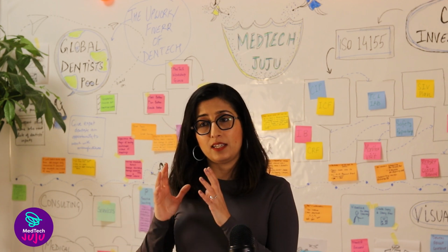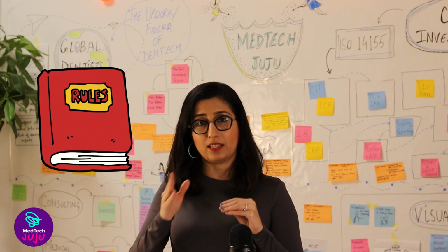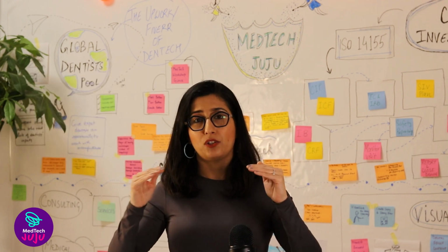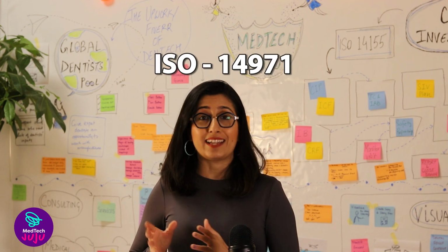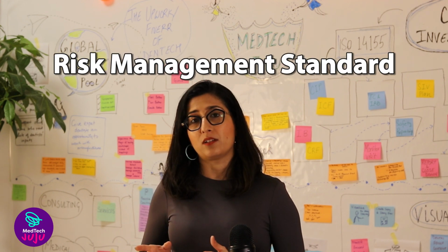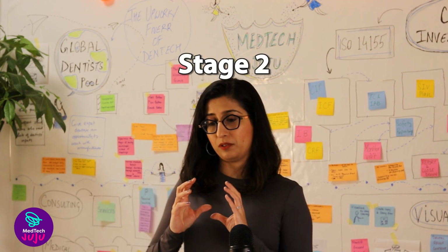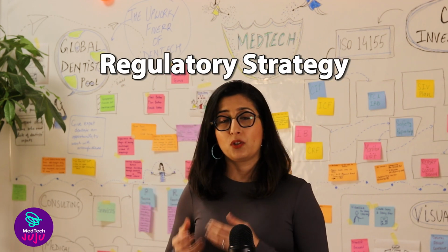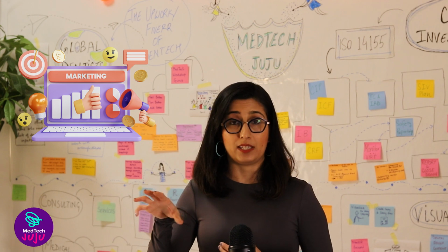And in the medical device industry, you have standards which help you navigate that thought process of defining and understanding risks, hazards, harms, etc. One of those standards is ISO 14971, which is the risk management standard. So in stage 2, you've kind of defined your initial risk management strategy and also your regulatory strategy. So you've already got an idea of here is the first market I want to approach with this device, or here are the first 2 markets I usually want to approach.